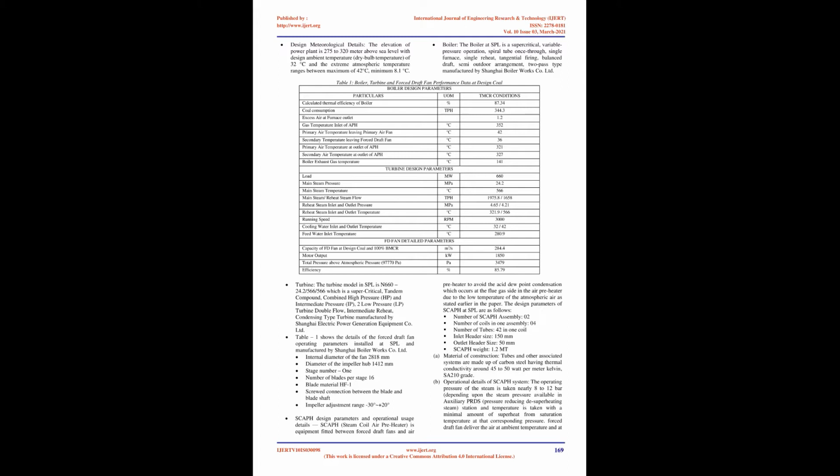But during normal ambient temperature conditions and full load operation of thermal units, SCAPH loses its usefulness and becomes a bulky burden as an auxiliary. This system imposes a resistance on the forced draft fans by the constant pressure drop across it.